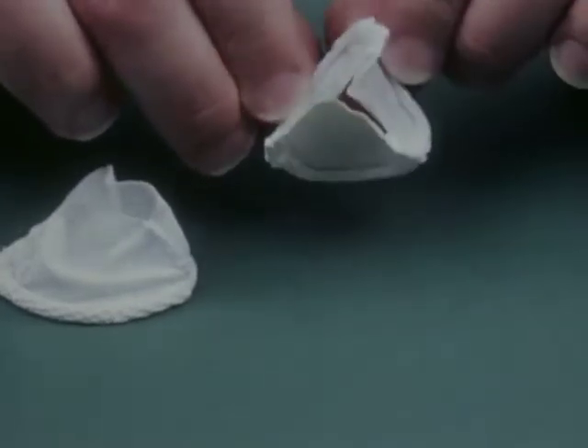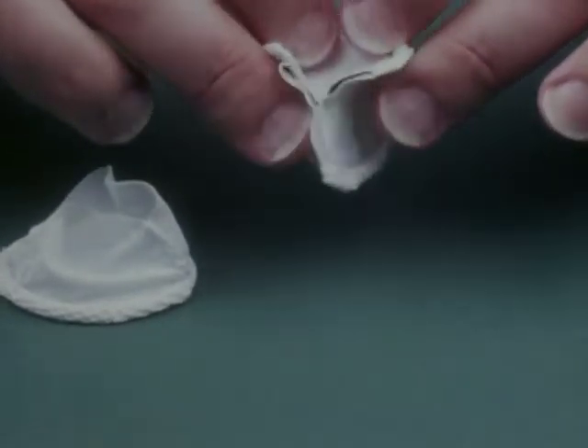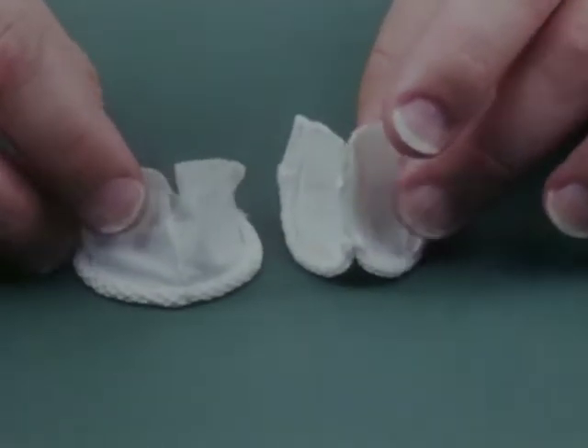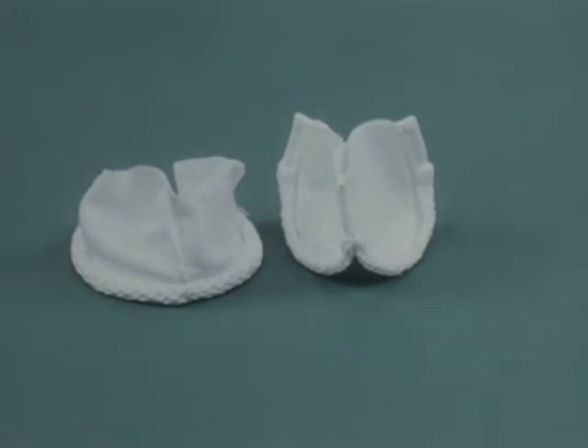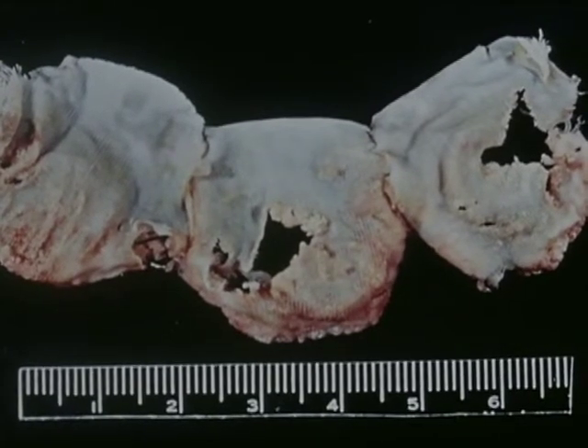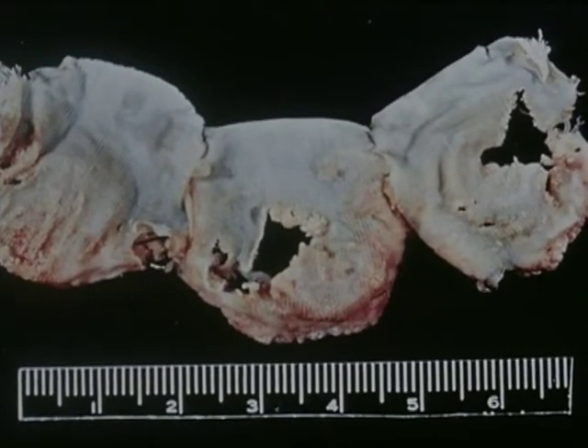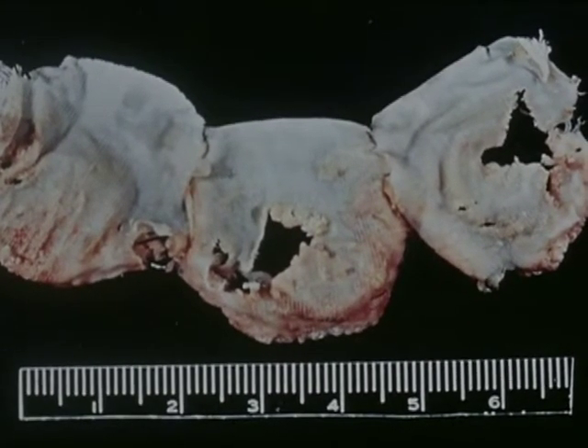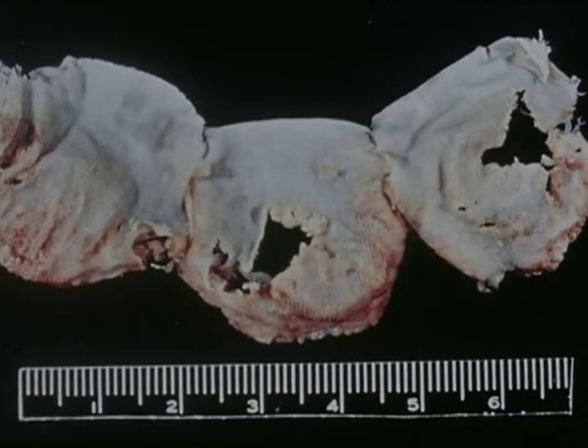Hemodynamically, this was a very acceptable alternative to the natural aortic valve. It was not obstructive, was totally free of embolic difficulties, and was completely silent. Unfortunately, after 12 to 24 months, these Teflon leaflets stiffened and cracked, resulting in recurrent aortic stenosis and regurgitation. Most of these leaflet valves were eventually replaced with later models of artificial heart valves.